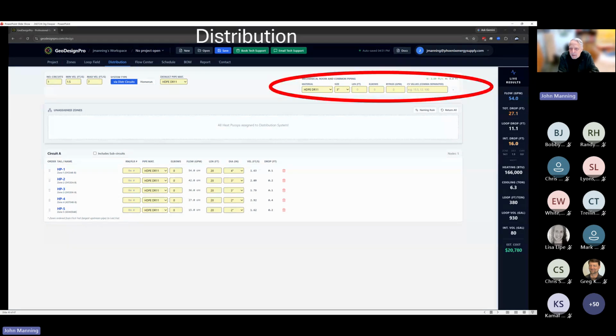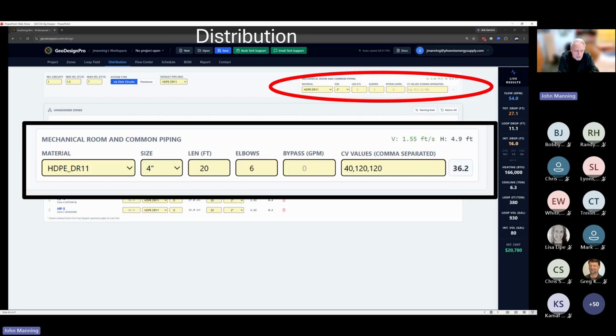We have also built in the capability of capturing what I call the mechanical room or the common piping in the system. You stipulate the piping material in your mechanical room, the diameter, the length, the number of elbows. You can specify a bypass flow rate if you want to have some sort of bypass filtration system, which forces the pump to pump more fluid, but we don't allow it to influence the pressure drops in the system, because that fluid is simply going to flow from the discharge side of the pump back into the suction side of the pump. You can enter CVs of all the various equipment you might find in a mechanical room, whether it's a strainer or an air separator or a triple duty valve. You can incorporate all that into your calculations.